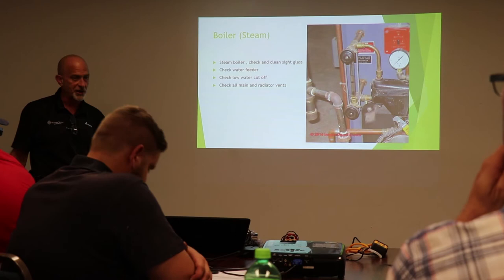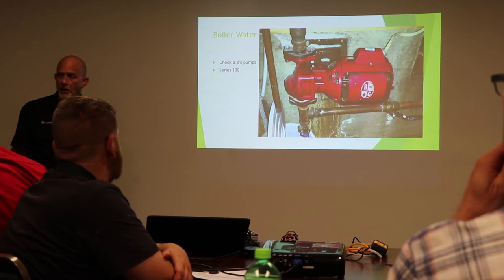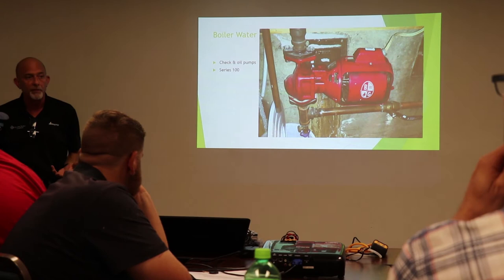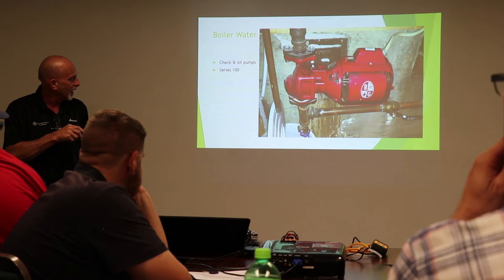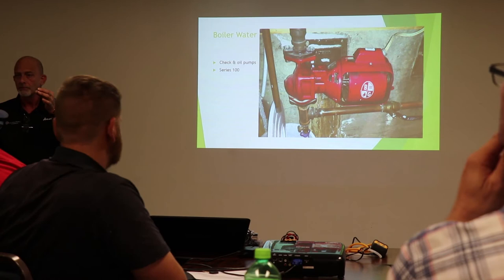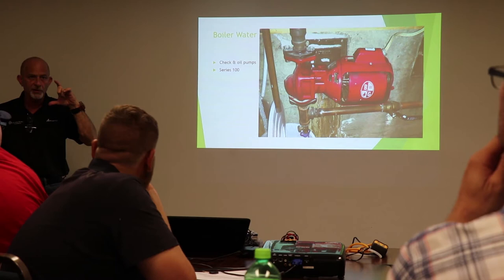Back to water boilers, we want to check our pumps. If we have a Series 100 pump still on the system, that's an oilable pump. I have an oil cap right here for our bearing, and we have a little oil plug here for our motor itself. A couple drops, guys. That's all you need to put in there. That tube that you guys buy from us will almost last a lifetime for a Series 100 pump.